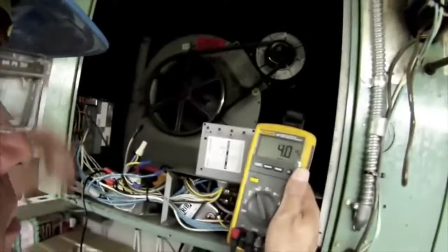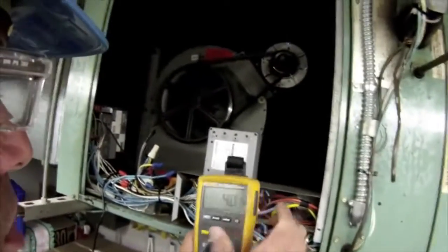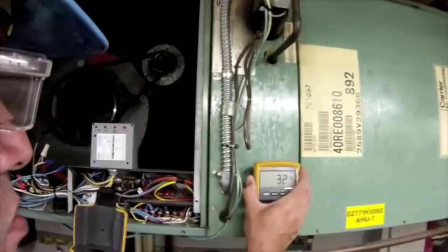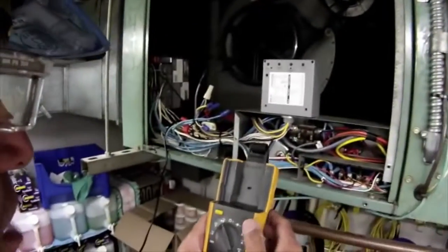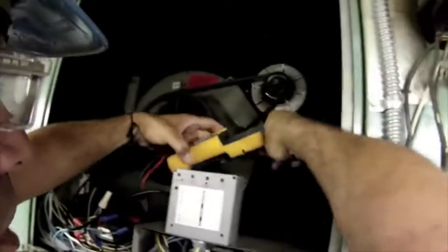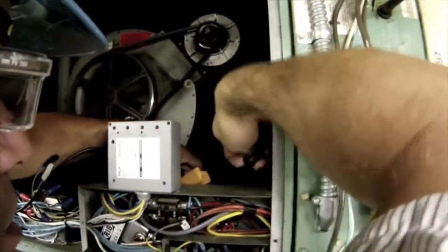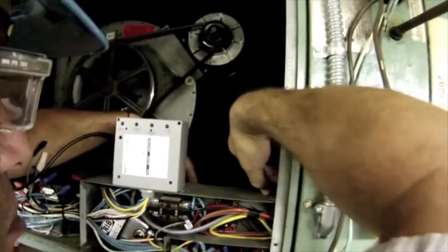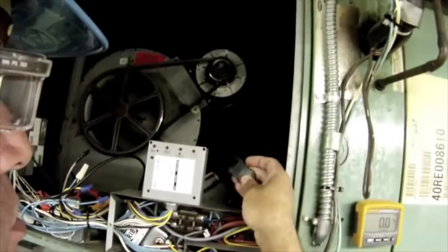My meter is on. And what I'm going to do is take the display off. Now this display is magnetic. I can set it off to the side right there. And I'm actually going to put the meter in the compartment. I'm going to use this great industrial strength magnet right here and just magnetize this to the electrical housing so nothing gets in the way of the fan motor or the belt. These magnets are great, really nice and strong.